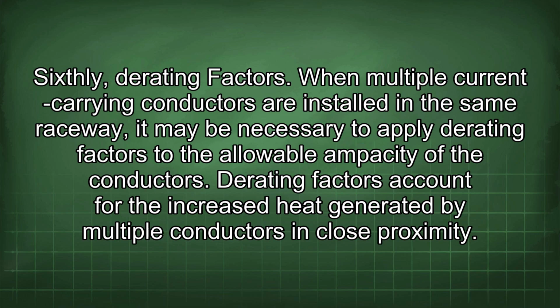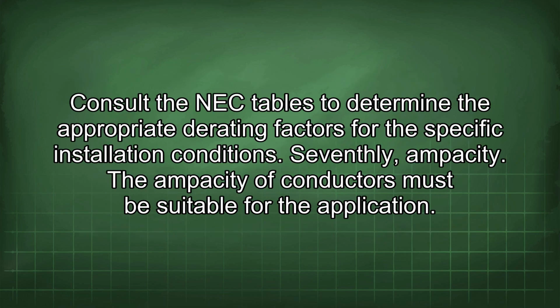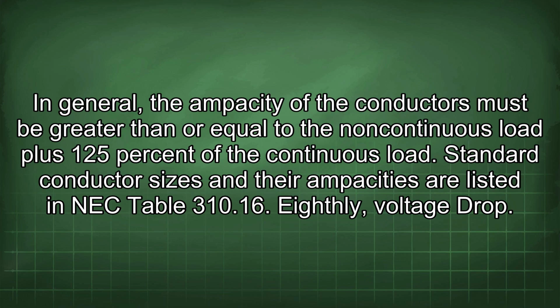Derating factors account for the increased heat generated by multiple conductors in close proximity. Consult the NEC tables to determine the appropriate derating factors for the specific installation conditions. Seventhly, ampacity. The ampacity of conductors must be suitable for the application. In general, the ampacity of the conductors must be greater than or equal to the non-continuous load plus 125% of the continuous load. Standard conductor sizes and their ampacities are listed in NEC Table 310.16.